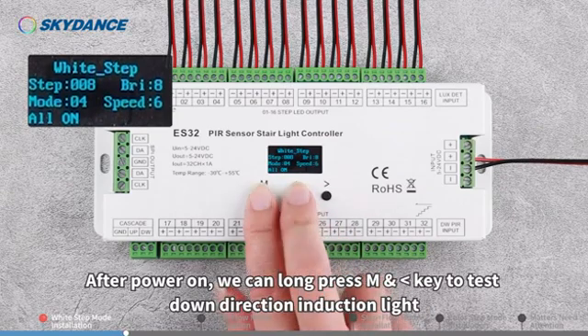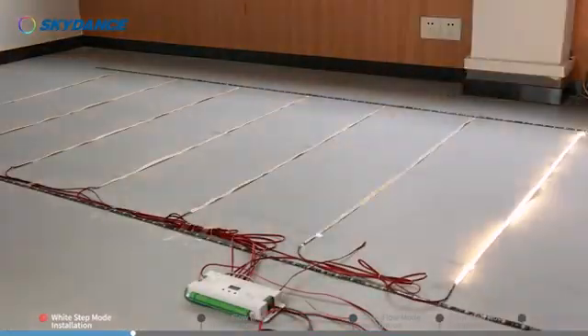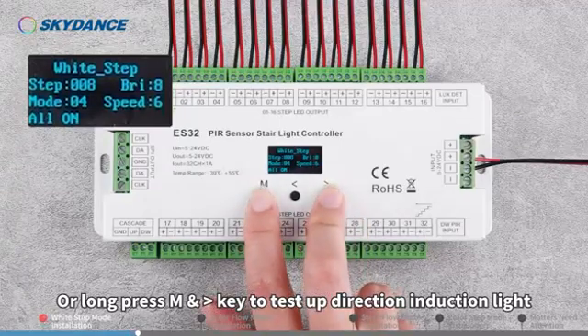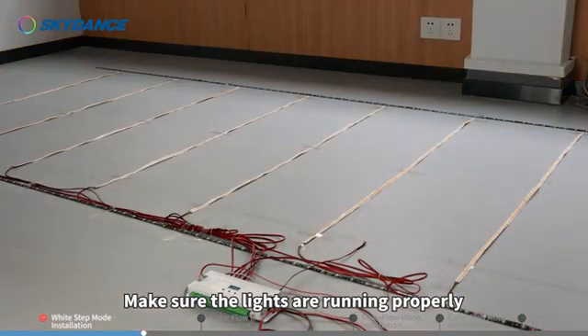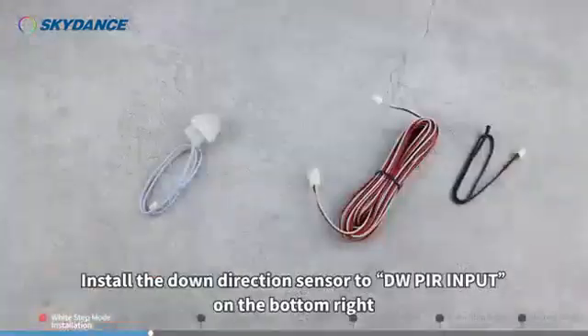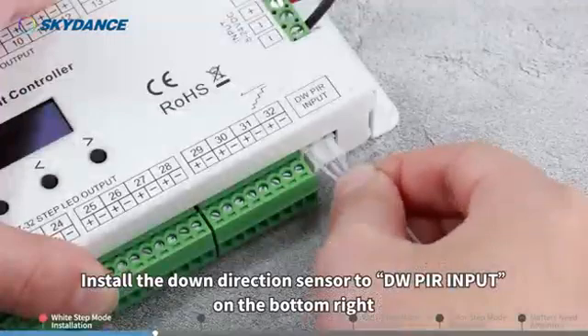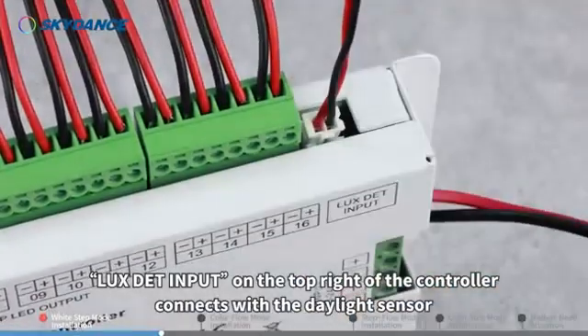After power on, long press M and the left direction key to test the down direction induction light, or long press M and the right direction key to test the up direction induction light. Make sure the lights are running properly. Then install the up direction sensor to the UP PIR INPUT on the top left of the controller. Install the down direction sensor to the DW PIR INPUT on the bottom right. The LUX DET INPUT on the top right of the controller connects with the daylight sensor.